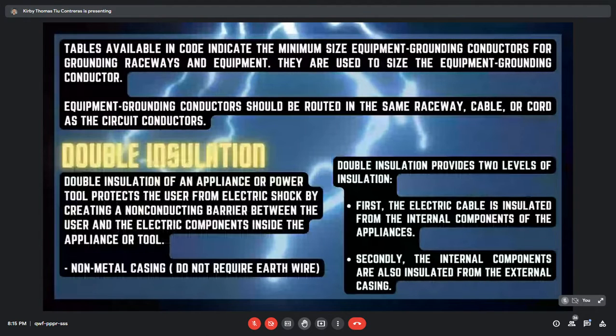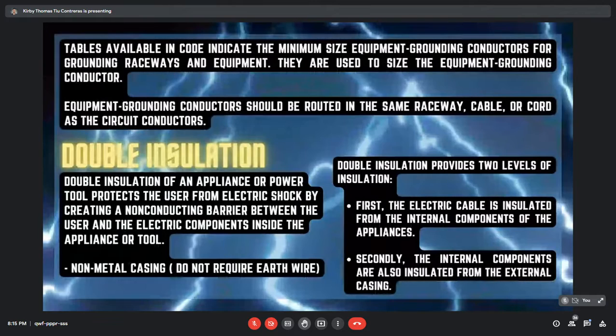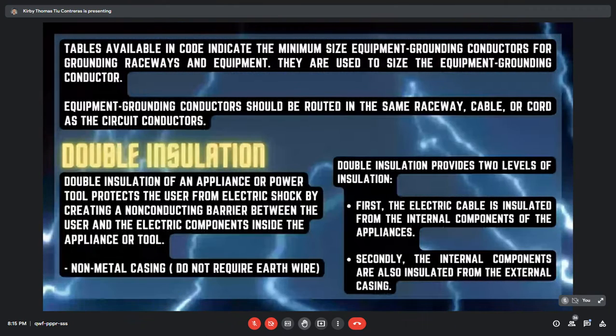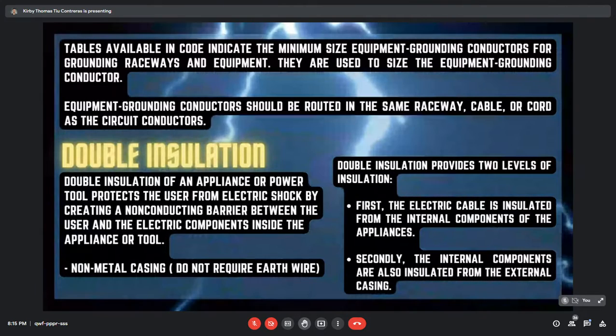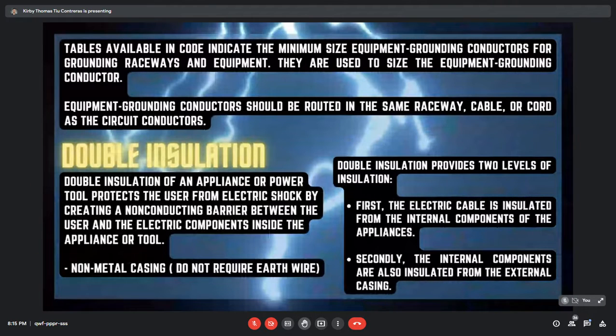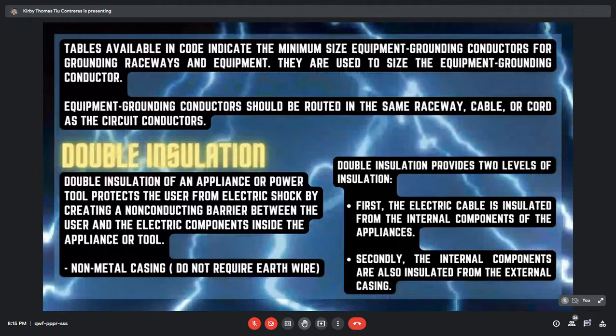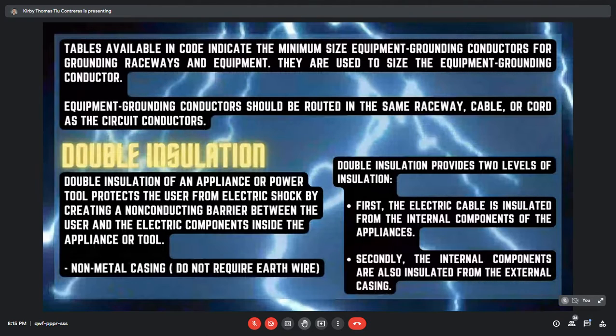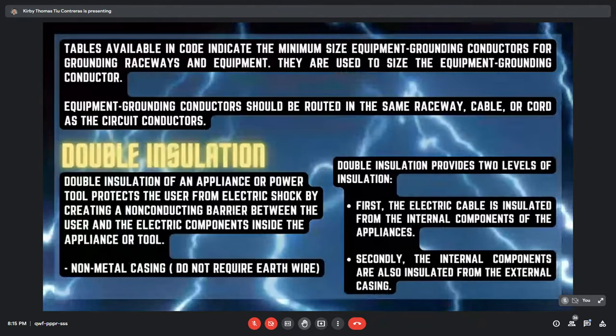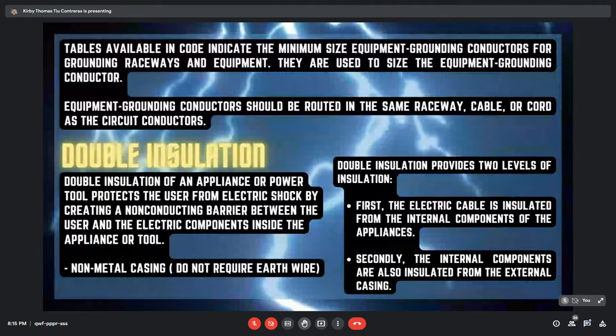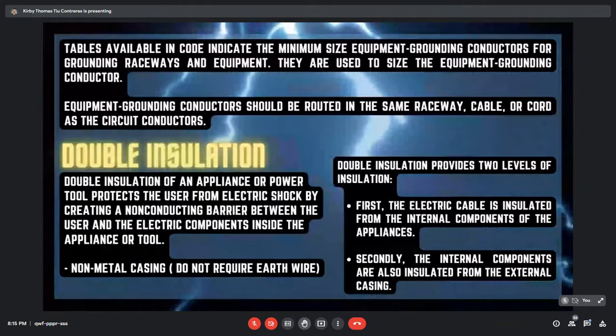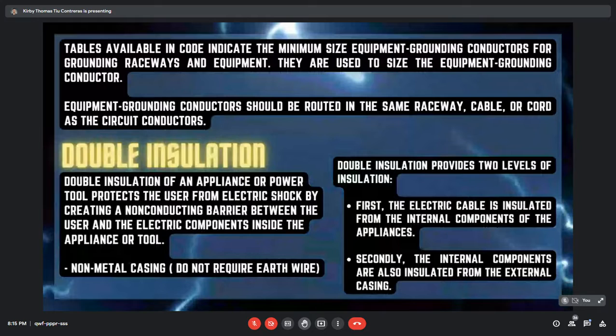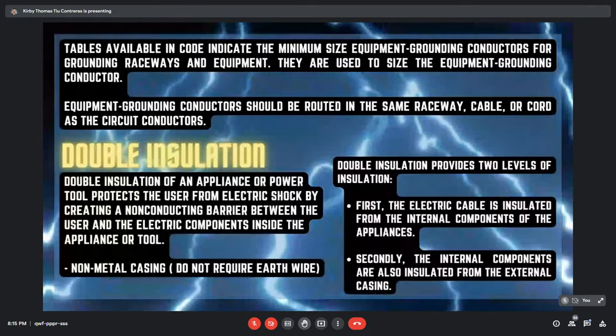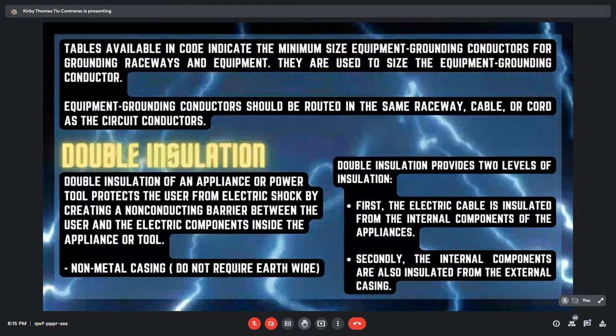Next slide. And we have tables available in the code that indicate the minimum size of equipment grounding conductors for grounding raceways and equipment. They are used to size the equipment grounding conductor. The equipment grounding conductor should be in the same raceway or cable as the circuit conductors. And lastly, double insulation. Double insulation of an appliance or power tool protects the user from electric shock by creating a non-conducting barrier between the user and the electric components inside the appliance or tool. It has a non-metal casing, so it does not require an earth wire.